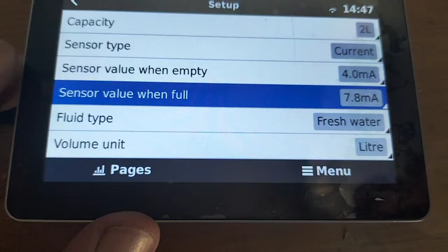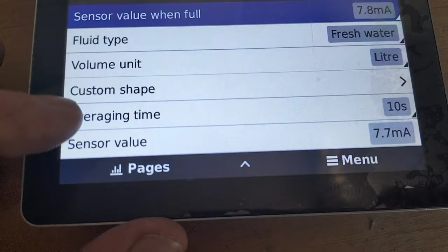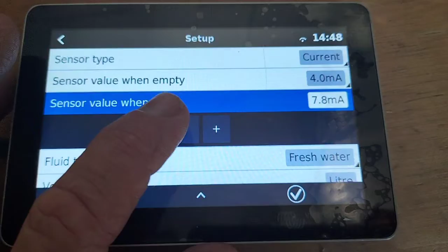And then we want to register when the sensor is full. So we want to know what that value is going to be. So what we'll do, let's come over here. Oh, there we are. So we're full tank of water other than what I splashed out. And what we want to know is what is the sensor value right now, 7.7 milliamps. Before I spilled a bit of water, the sensor value was actually 7.8 earlier on when I did my first practice run. So let's change that, 7.7.